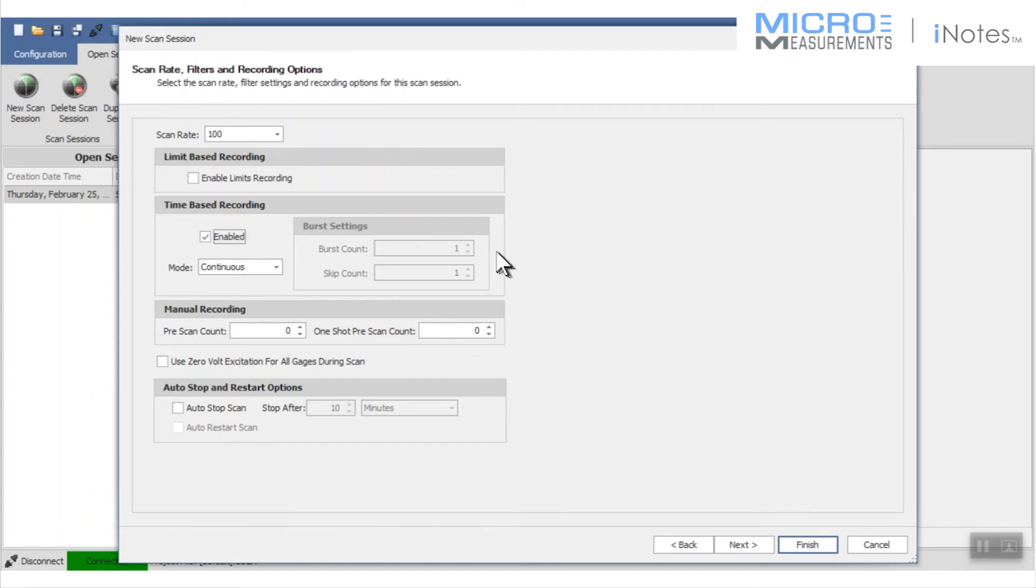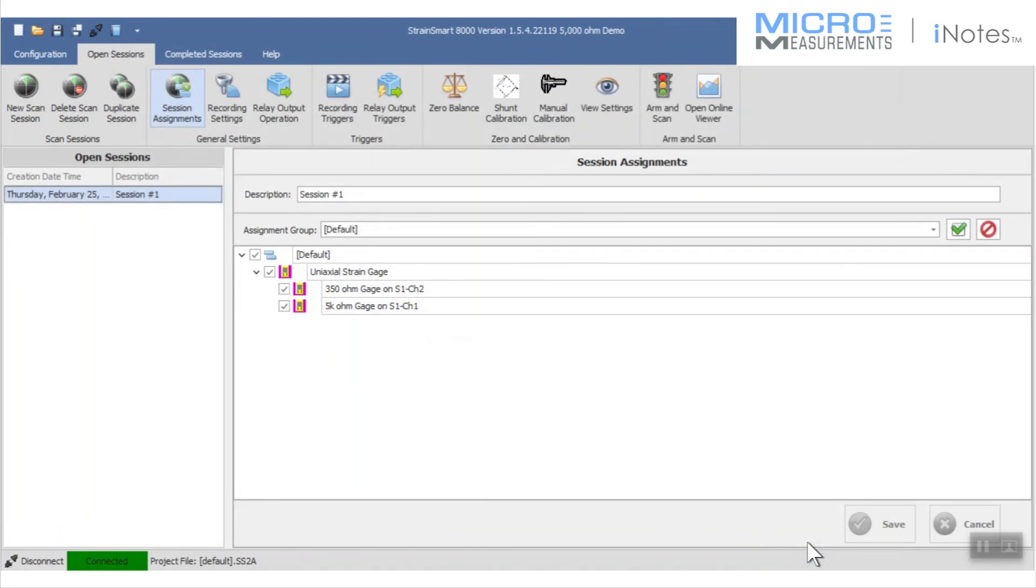There's lots of options here where you can capture pre-sample or pre-count before something happens. Trip levels, you can have it not record things for days, hours, weeks, and then do a real fast burst at some point, or do a fast burst when something happens. I pretty much know that I'm finished here, so I'm just going to tell it to finish up.